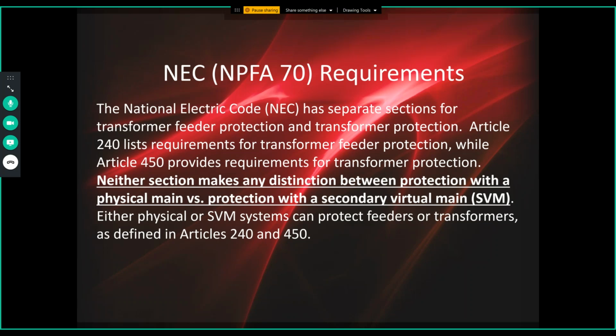Neither of these sections, I want to be clear, makes any distinction whatsoever between protection with a physical main versus a secondary virtual main. And either a physical or secondary virtual main can protect feeders or transformers as defined by Articles 240 or 450. I've, on some occasions, had to make this case to authorities having jurisdiction, and so far I'm batting 1,000. I've never lost the argument. Sometimes it takes a little bit of explanation, but I've always won the argument.